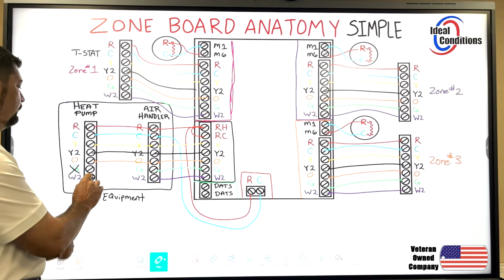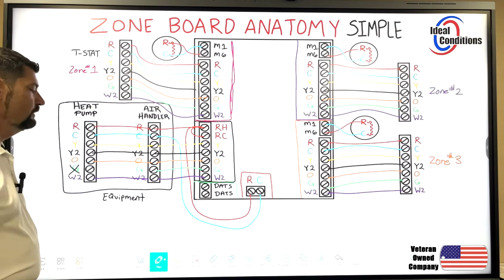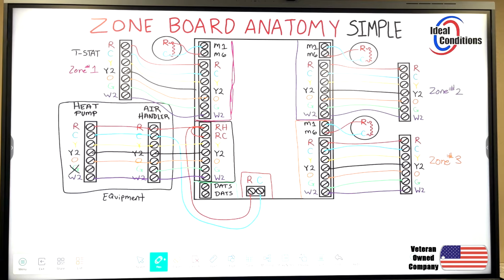The heat pump is sending the signal for W2 to be energized during a defrost. So even though you see it all connected there, it's all in parallel at that point, but the signal flow is what I'm talking about. Where's the message coming from? This is how you would wire the zone board if you're using one transformer.